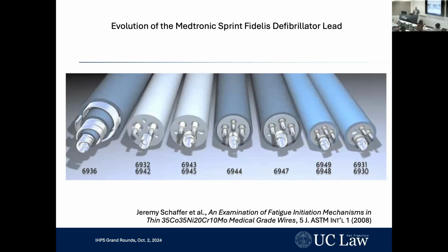And this was rapidly adopted by the medical community. And I was one of those people, because I was an electrophysiologist and this is what we used. It was pushed as: thinner leads have to be better because there's less obstruction of veins, and they're easier to remove if there's a problem. It turned out that the failure rate for these was about 4 times what the old lead was. And that was only discovered after about 300,000 people had received these. Right? And so you have that same kind of risk in the high-risk device world.